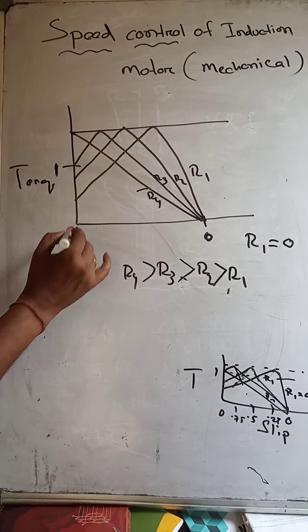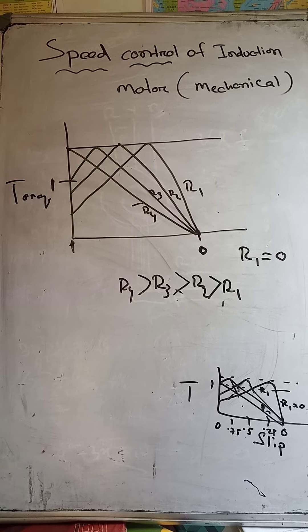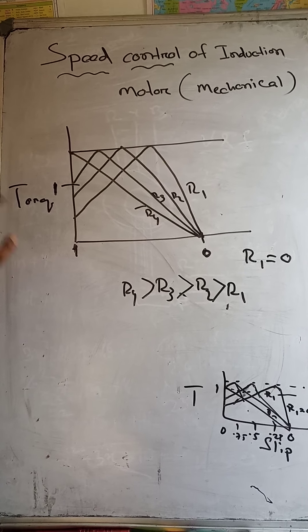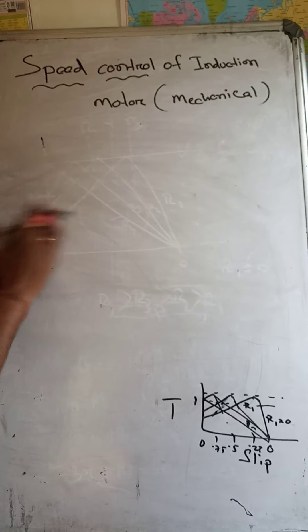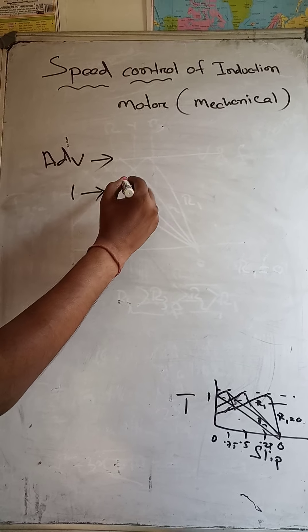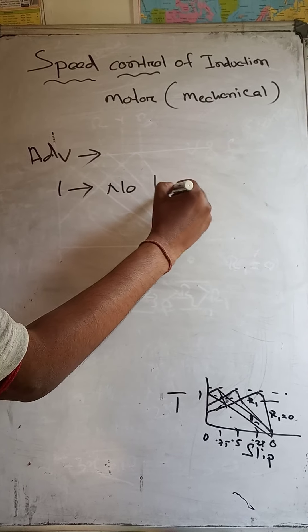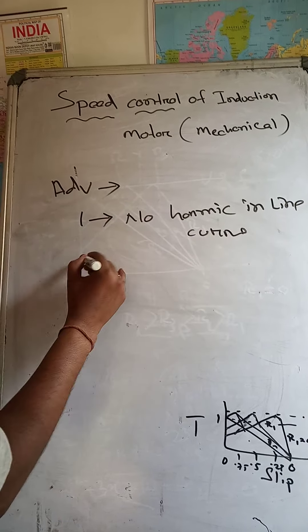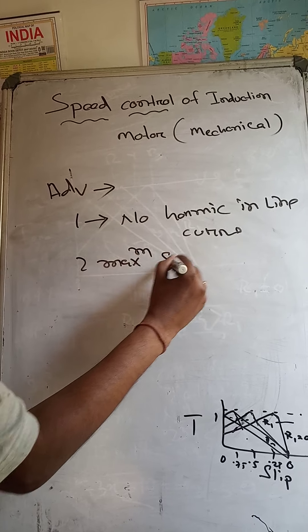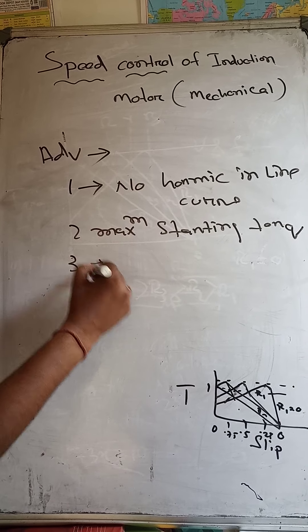From this graph, torque is at maximum and slip is at maximum. You can understand that the speed of a slip ring induction motor can be changed by changing the resistance in the rotor circuit. The disadvantage is that you cannot change the speed very smoothly. The advantages are: no harmonics in line current, maximum starting torque, and smooth starting.